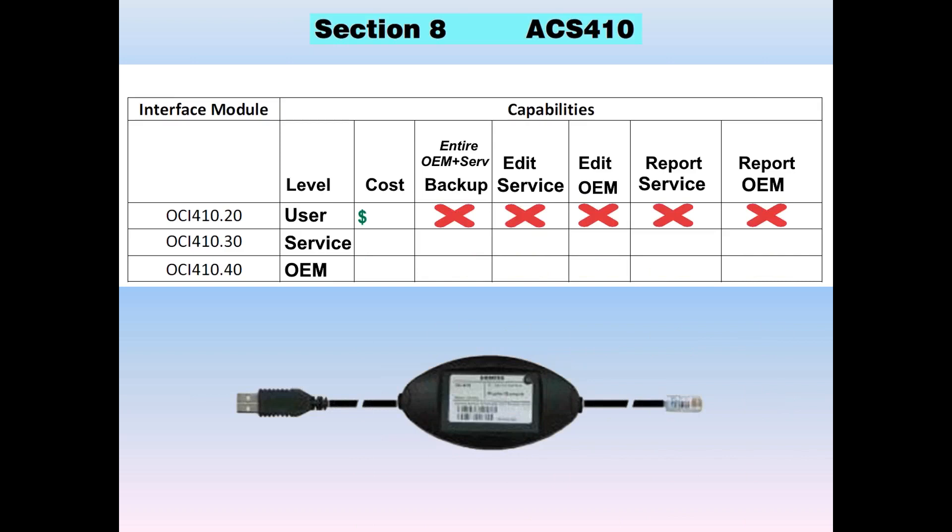If you take the user level OCI, that is the lowest cost, but for the lowest cost you get the least features. That one is rarely sold simply because you can't do a backup. If you're going to invest in an OCI, you want to be able to do a backup to the PC. The only benefit to having an OCI 410.20 would be viewing fault history in one big splash on screen. You can see all the faults and view all the user level parameters, but there's no way to back it up.